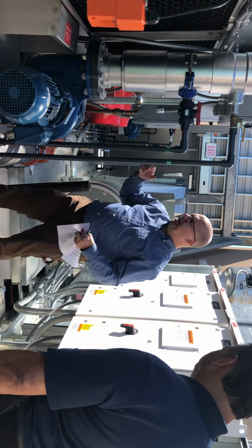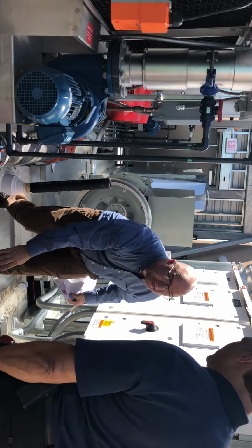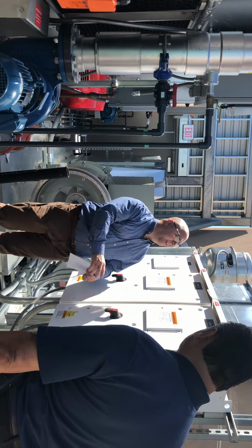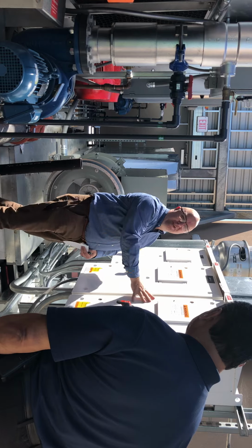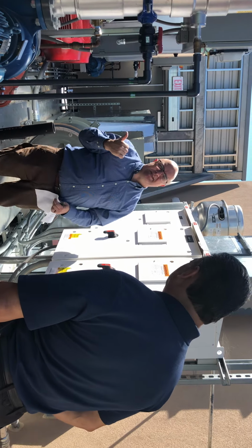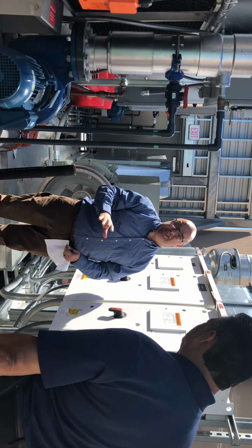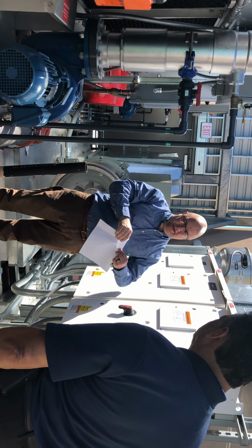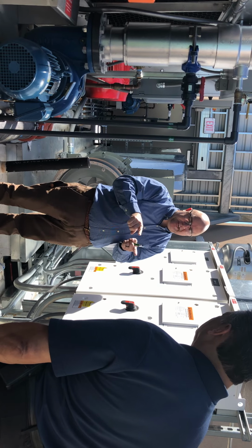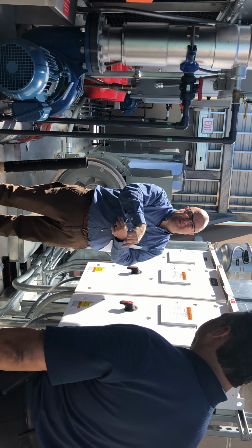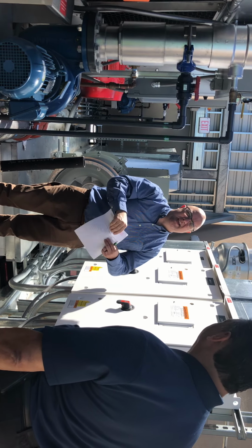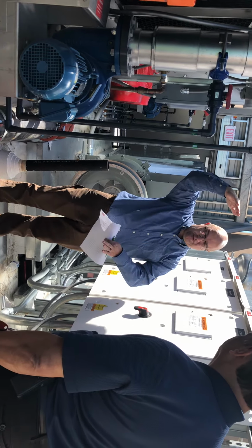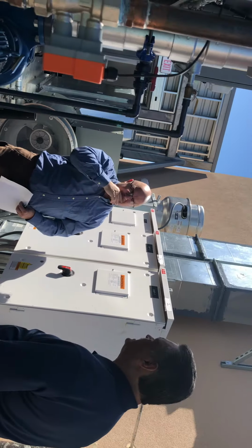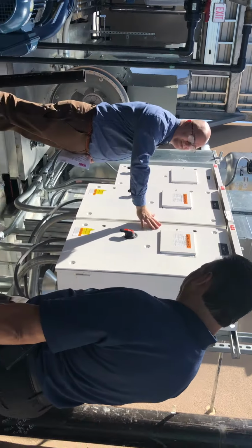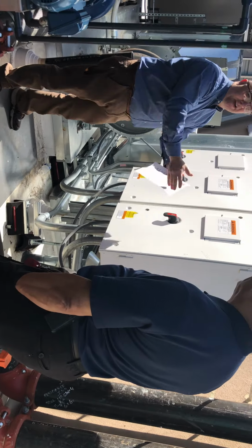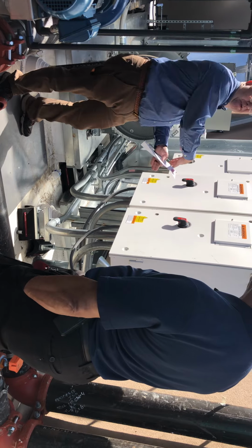The two big pumps that are pushing that water through these big pipes, those are those two pumps right there, and they're controlled by drives here. Okay. I do control those two big pumps. There is a pressure sensor, and we'll show that later. It's in the garage. And so the water pressure from the supply to the return, I control those pumps to make sure there's plenty of water all the way down on the second floor, to make sure that all the heat pumps between the roof and the second floor have plenty of pressure water to operate. Gotcha. Yep. So these pumps are under my control. We do turn them on and off in turn, and if one fails, the other one picks up. Yep.